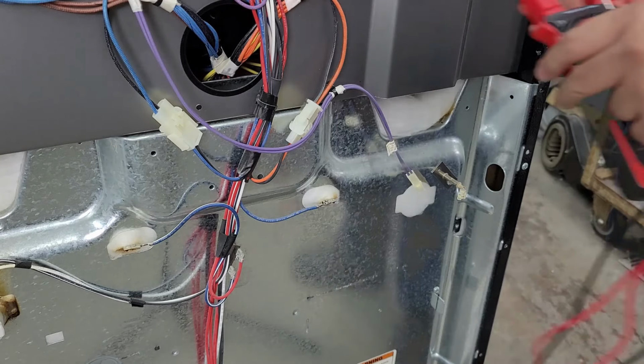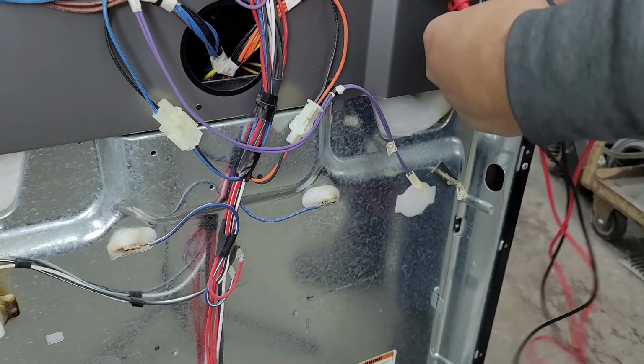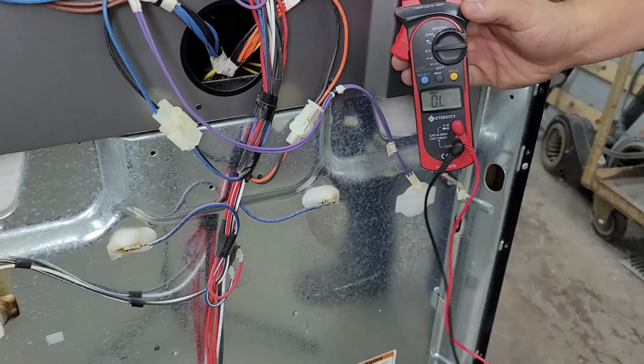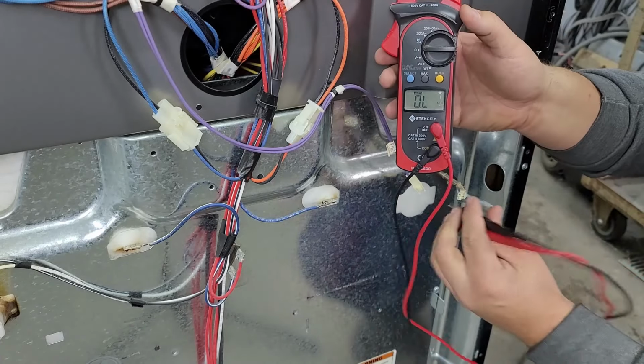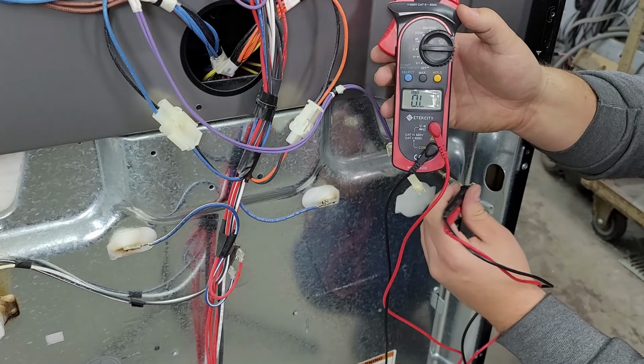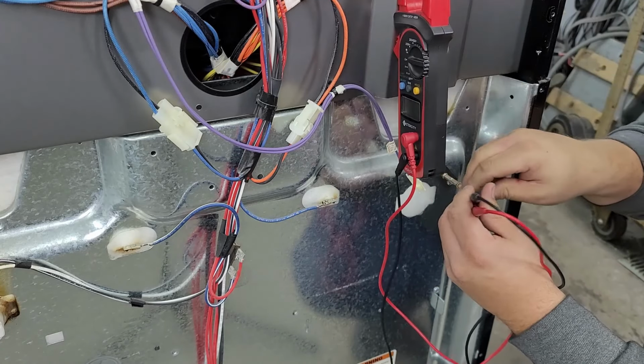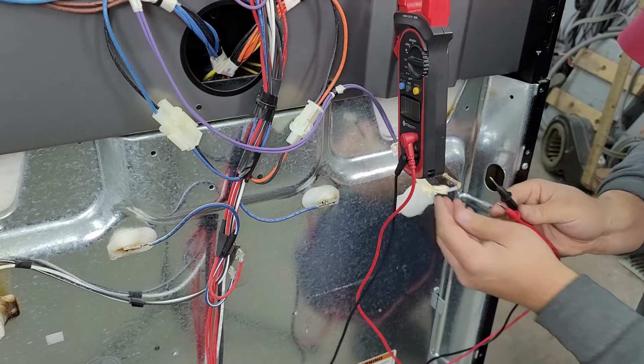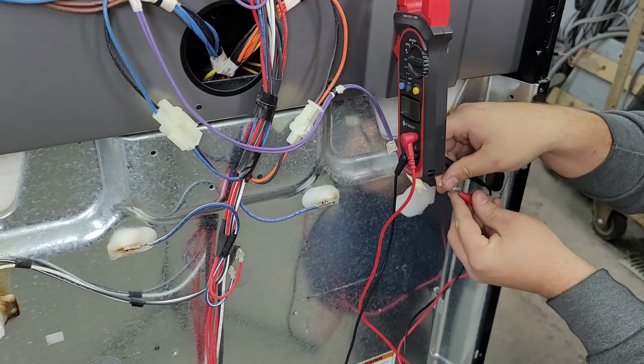of your stove. With the thermostat unplugged, you want to take your multimeter and set it for ohms resistance. On many thermostats, you're going to quickly find out that your multimeter leads will not fit in the extremely small connectors on the thermostat. One way I use to test then is to stick the multimeter leads on the back of the connector of the thermostat rather than the front.